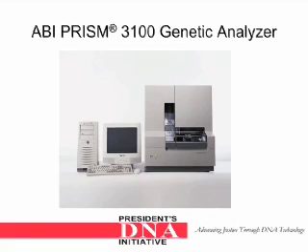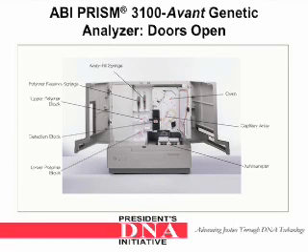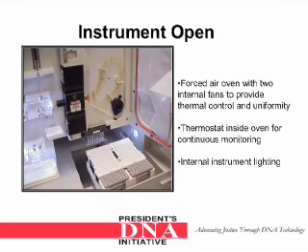Here is an example of what an ABI Prism 3100 Genetic Analyzer looks like. Similarly to the 310, the 3100 Avant has an auto-sampler for the samples. Instead of one capillary, it now has a capillary array, and it has an oven which gives better temperature stability. Also, it is able to deliver more polymer with two syringes instead of one.